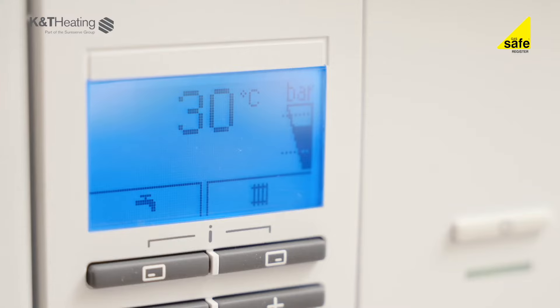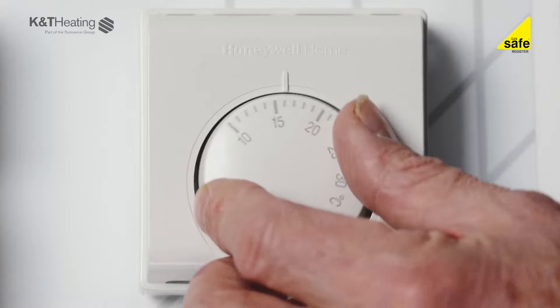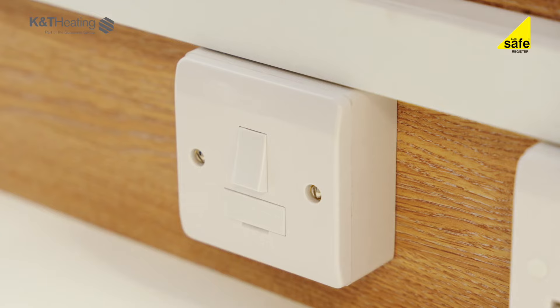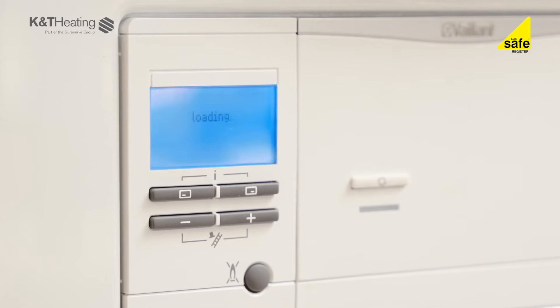Having established that you have electricity, check your boiler and controls. Are there any control display lights on the boiler visible? If yes, then the boiler has electricity — therefore you need to turn on your heating. You can do this by turning your programmer to 24 hours or constant and by turning up your room thermostat. If there are still no visible display lights or indicators on the boiler, check the boiler fuse spur or power switch. This should be adjacent to the boiler. Has it been accidentally turned off? Switch it on again and check the boiler display or controls for any indication of electrical power.